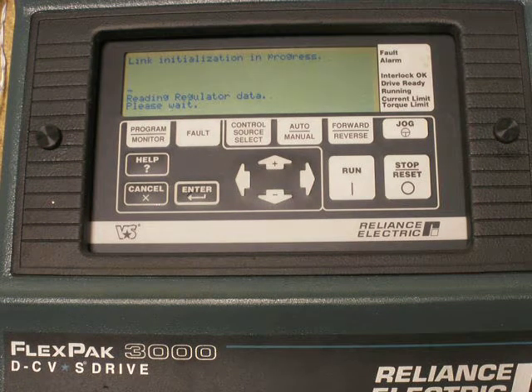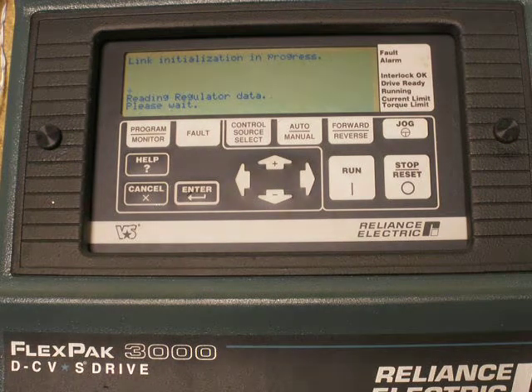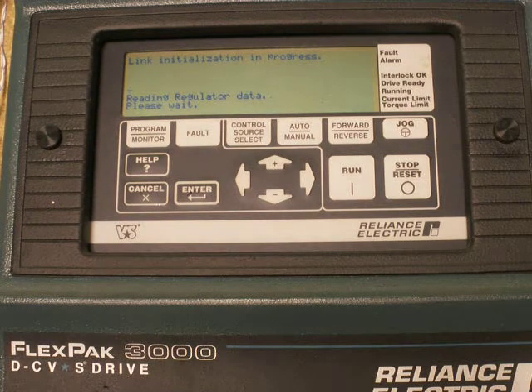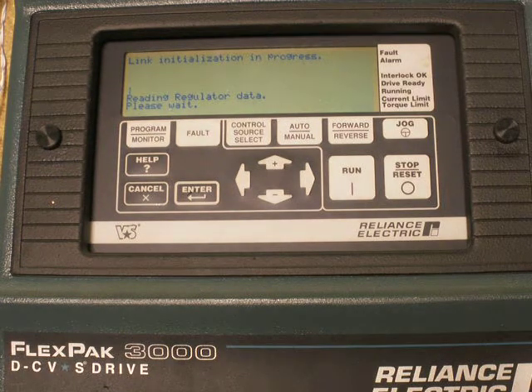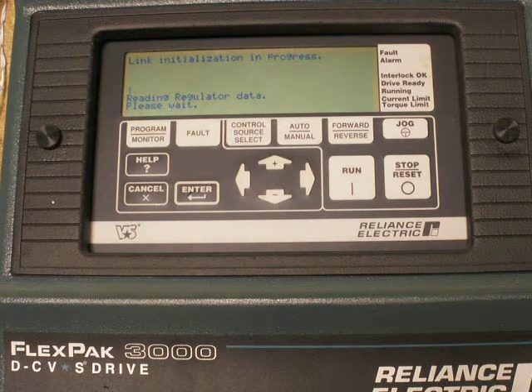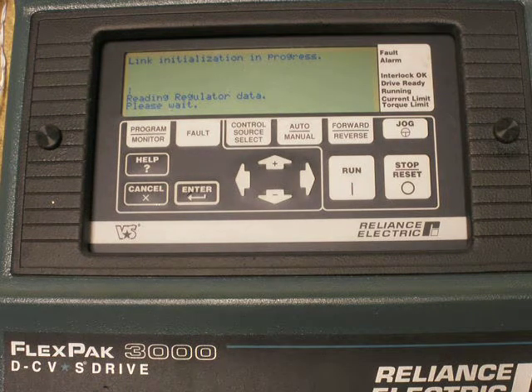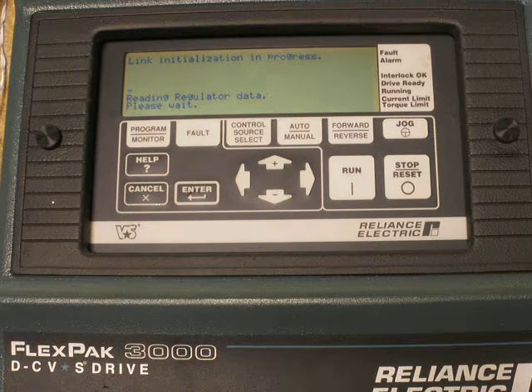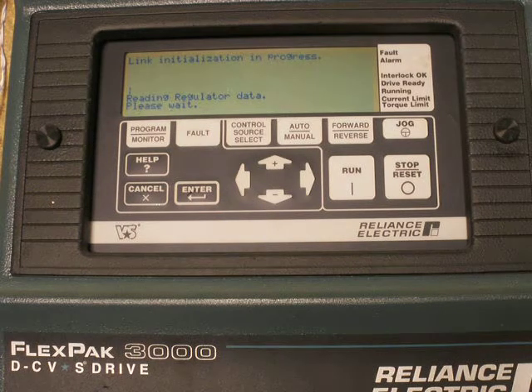At this point in time, the link initialization is in progress. It's going to attempt to talk to the drive itself, which is not there. But we should not receive a microbus fault, and we should be able to look at our error logs to be sure it's just standard drive faults and errors we should be seeing.